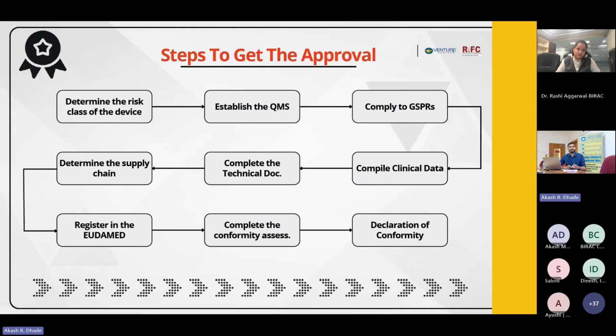Once you do that, your authorized representative will help you register your establishment in the database. It is a very mandatory and basic requirement that your entity should be registered in the database. Along with that, whatever device you want to sell, the CE marked device you want to sell in the European market, should be listed in the database. And that helps the European population. They can also access this database directly. They can search with your device name and see how safe and how good your devices are, and if there are any adverse events and recalls.